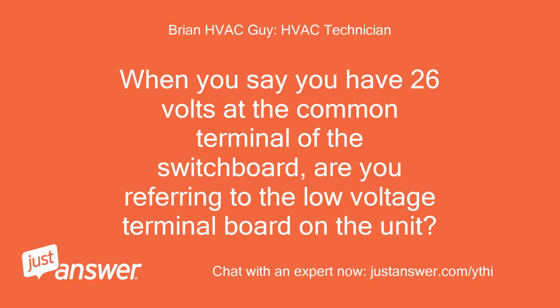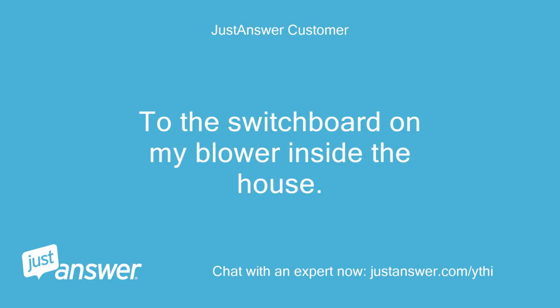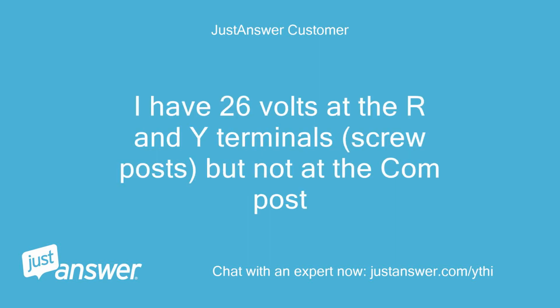When you say you have 26 volts at the common terminal of the switchboard, are you referring to the low voltage terminal board on the unit? To the switchboard on my blower inside the house. I have 26 volts at the R and Y terminals, screw posts, but not at the COM post.